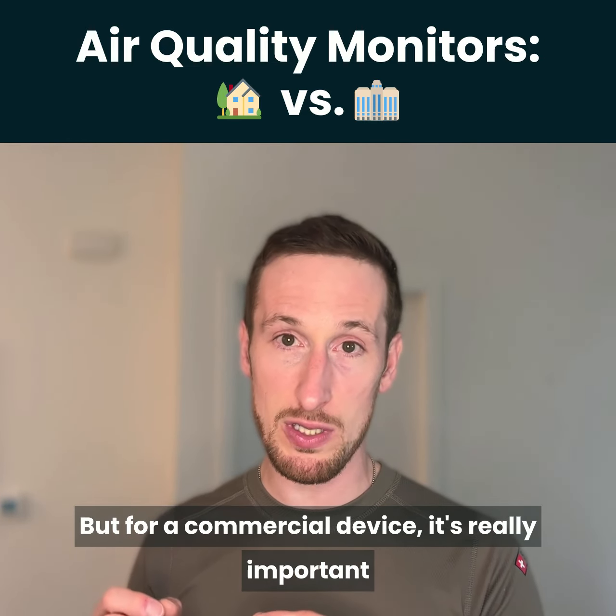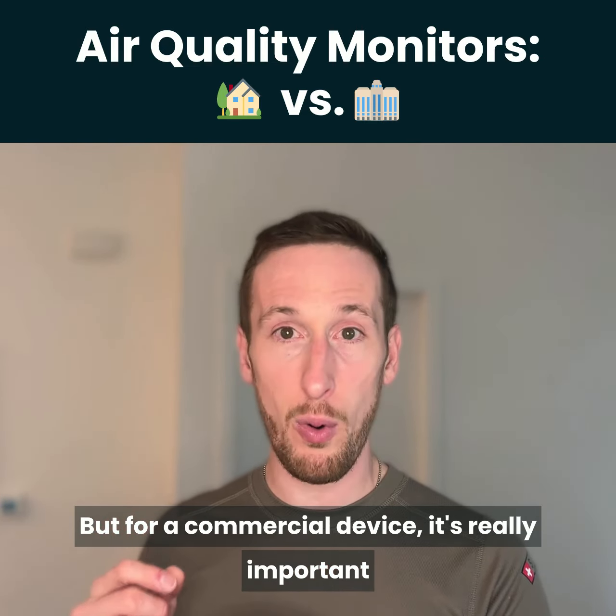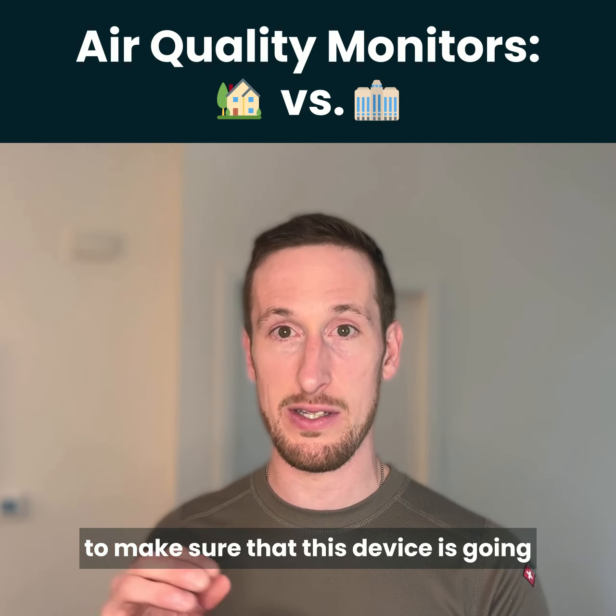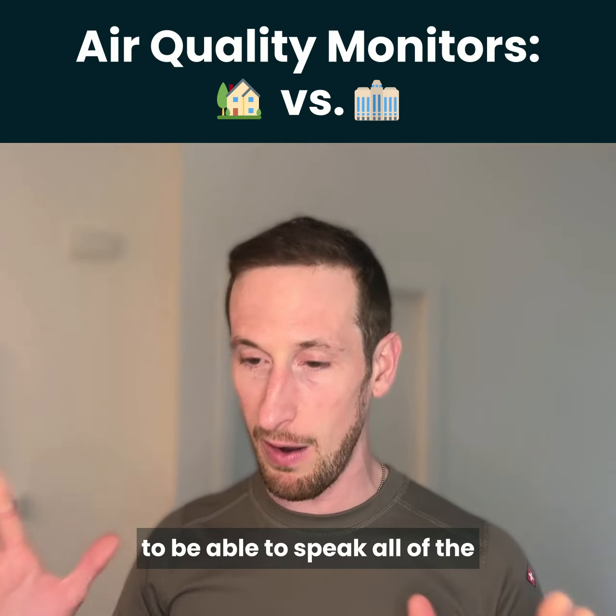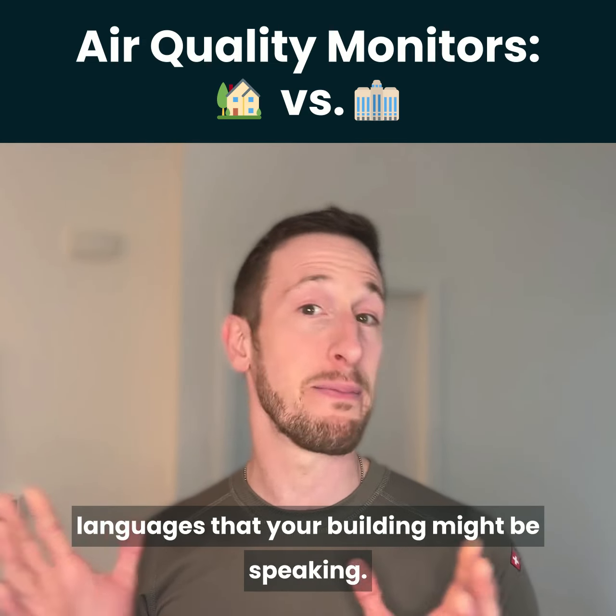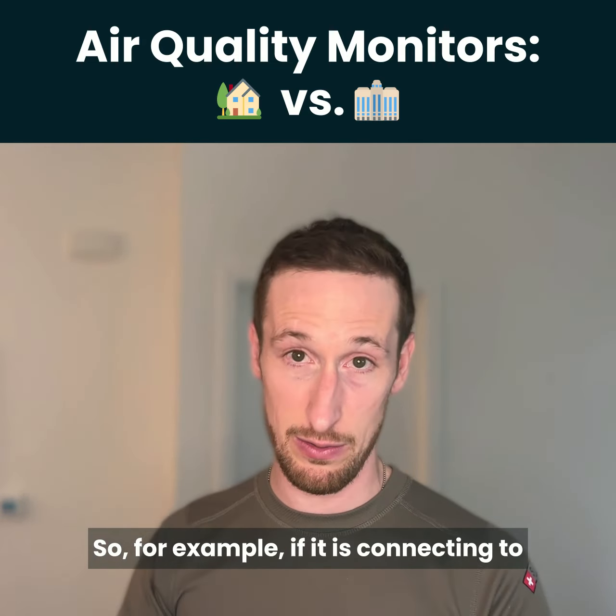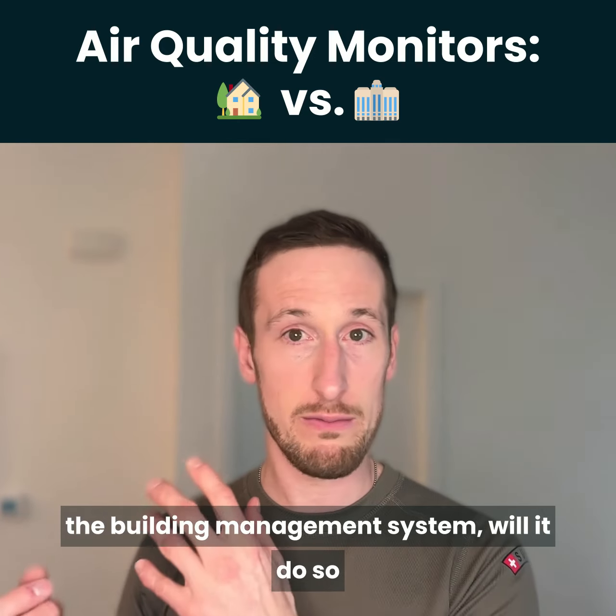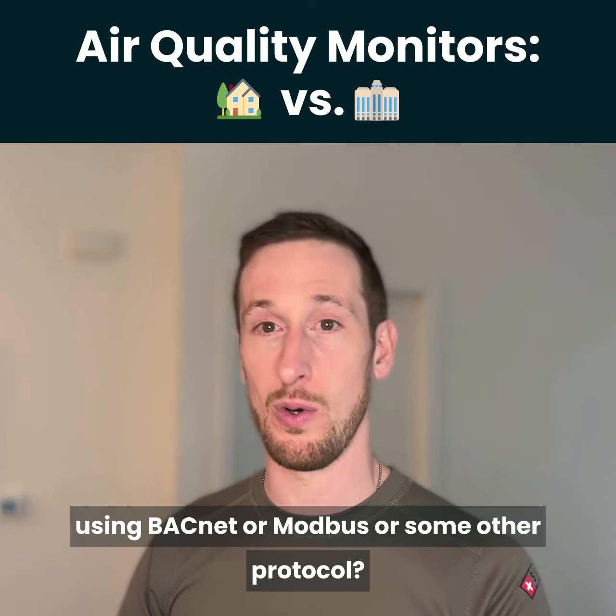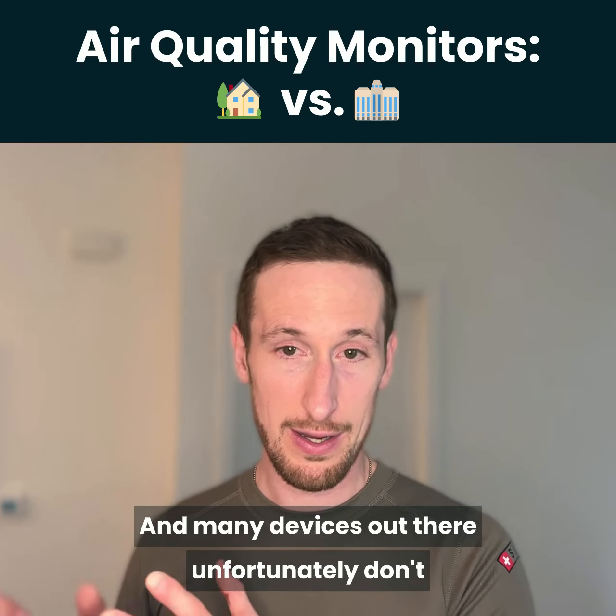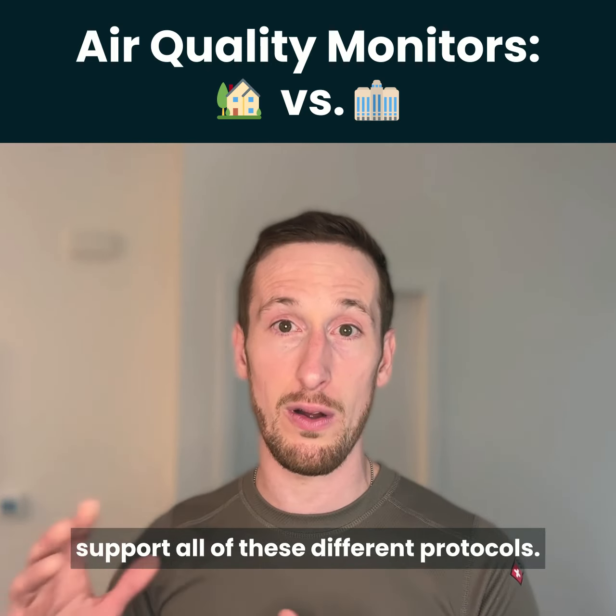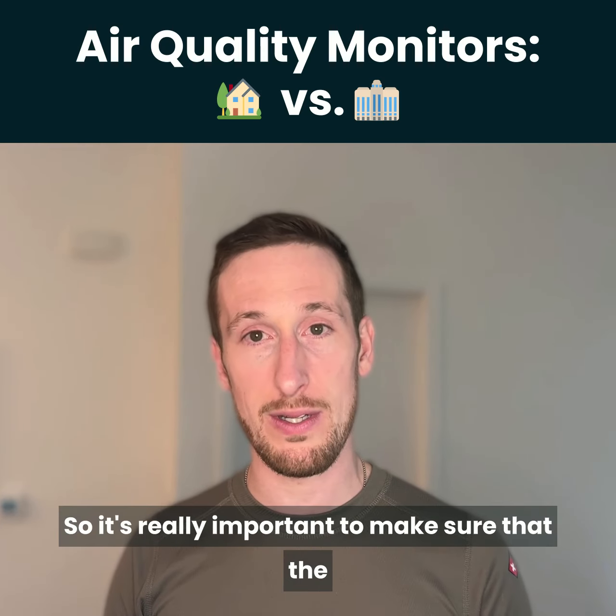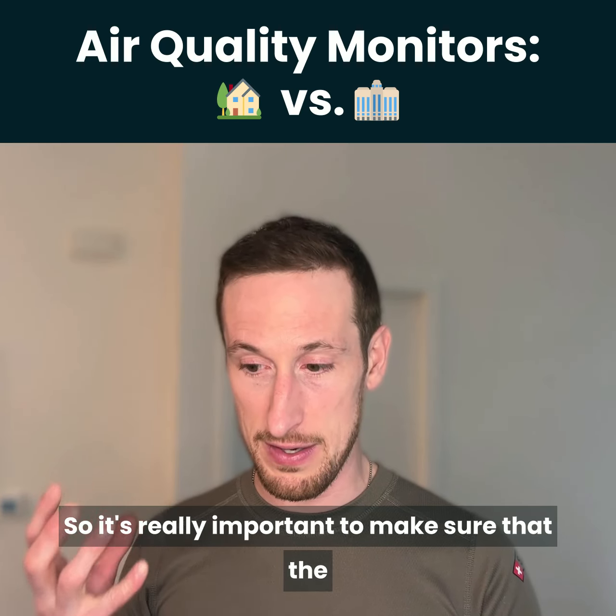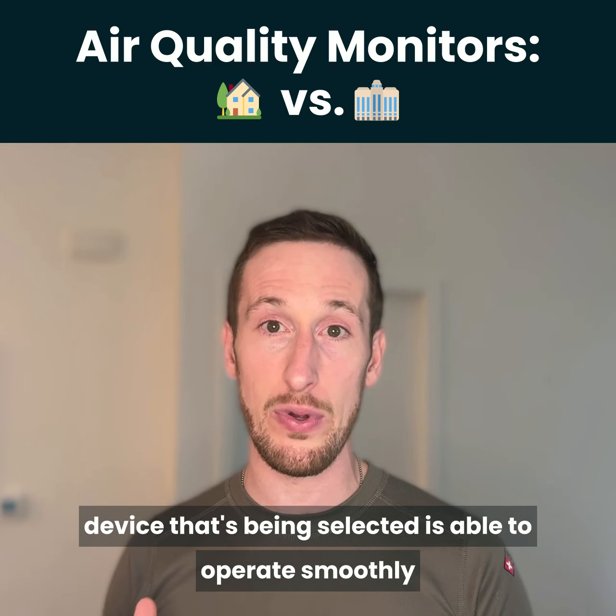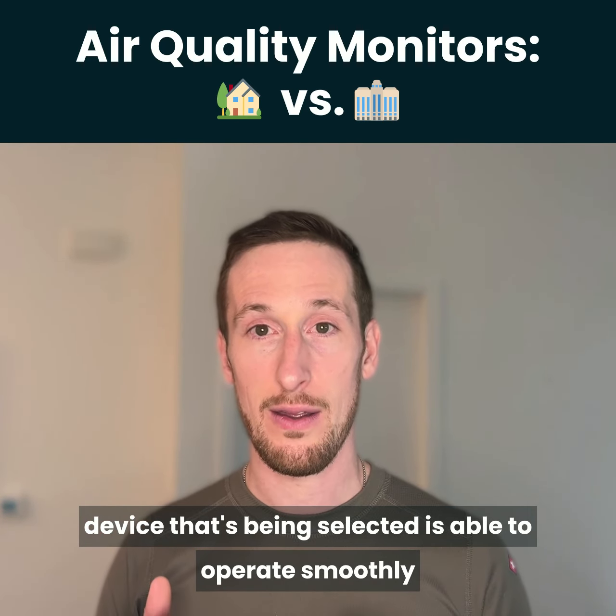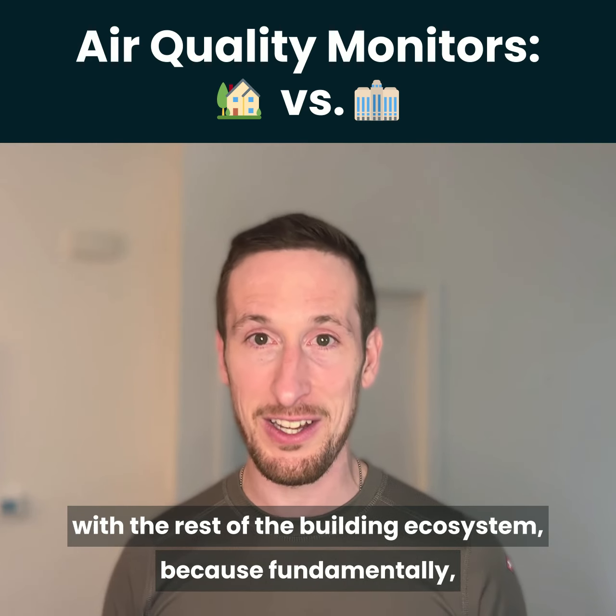But for a commercial device, it's really important to make sure it can speak all the languages your building might be speaking. For example, if it's connecting to the building management system, will it do so using BACnet or Modbus or some other protocol? Many devices out there, unfortunately, don't support all these different protocols. So it's important to make sure the device selected can operate smoothly with the rest of the building ecosystem.